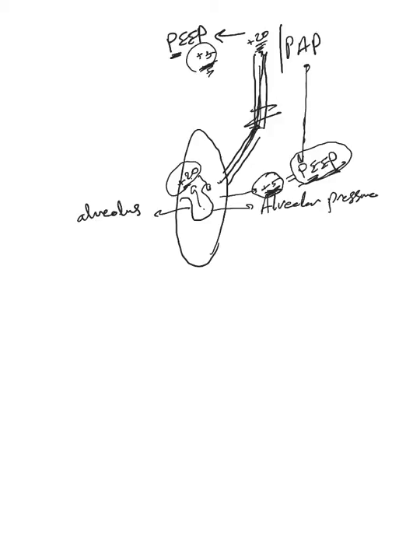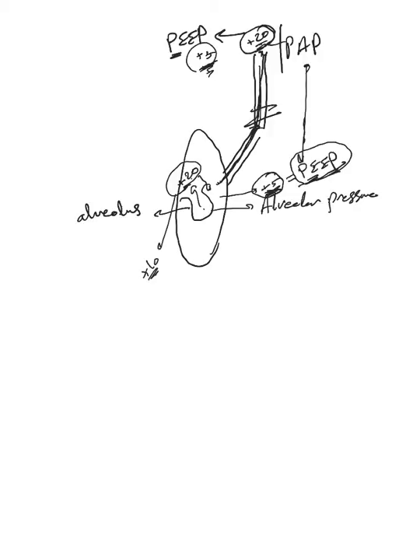That means there is still flow. Let's say this went to plus 10 and is still flowing, and the ventilator decides we're going to deliver a breath for one reason or another. Now the pressure here becomes positive 20 and now it's positive 10, that means now the air will start flowing in despite the fact that the pressure in the alveoli was not allowed to go back to the PEEP.